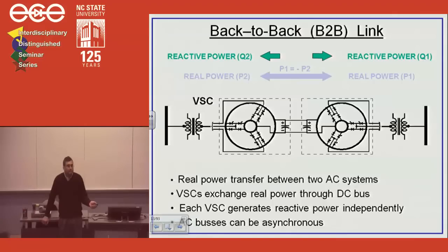Do you have different generating plants that generate slightly different frequencies? Let's say one would be 60 plus 10 to the minus 6, and the other would be whatever. Yes, we have that because we want to enable parallel operation of generators, and they would sense frequency to balance their loading. But typically that would be very, very small. They're very closely monitored between the different power plants. Absolutely, we do not want any difference in frequency. In fact, the frequency specs are as tight as less than 0.2 hertz. Okay? But this is a real thing.